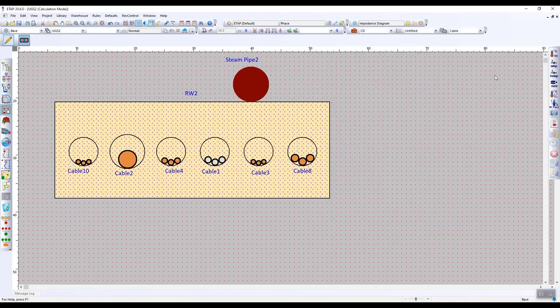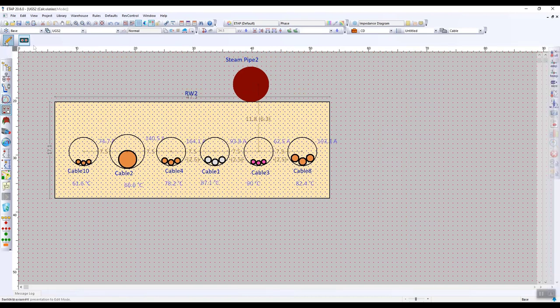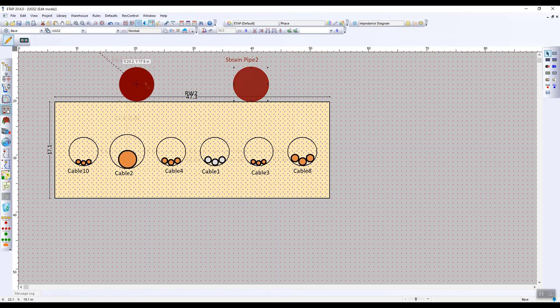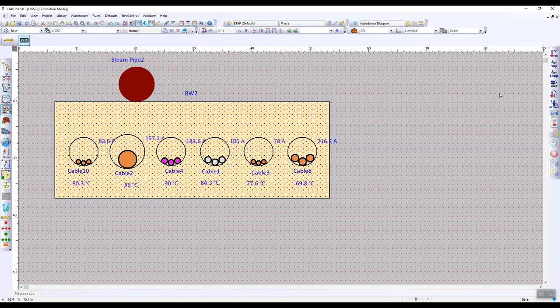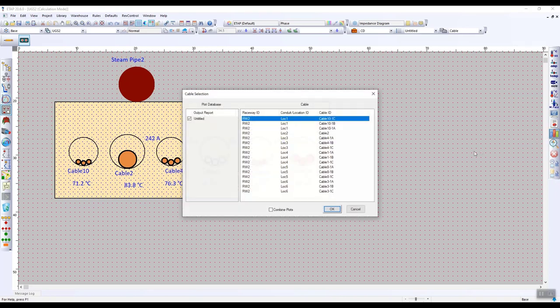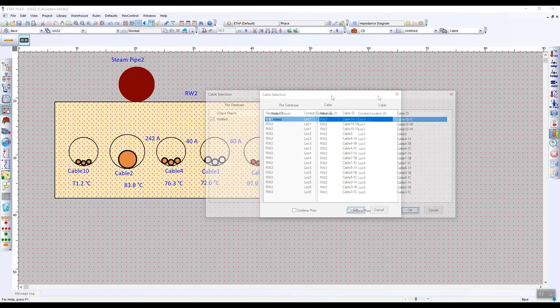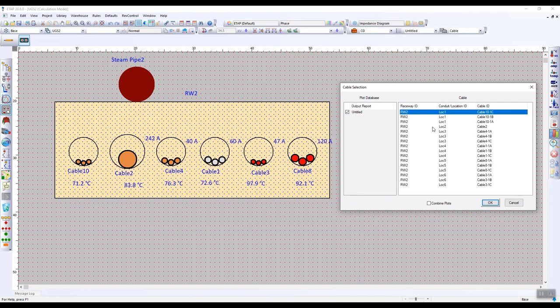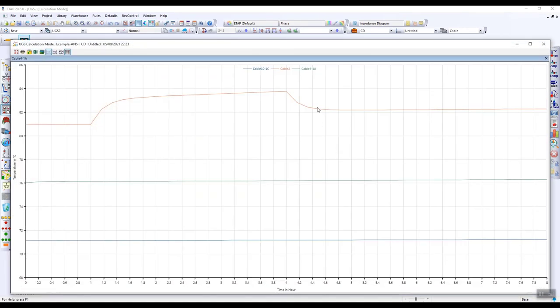We can also move the steam pipe around the raceway and we can see how that affects the uniform ampacity calculation. In the first view, we saw there is more thermal heating around cable 3, but when we moved the steam pipe to the left, we saw there is more heating around cable 4. We can also graph the transient temperature calculation plots. We can select a single conduit or multiple conduits and graph each one individually or combine the plots.